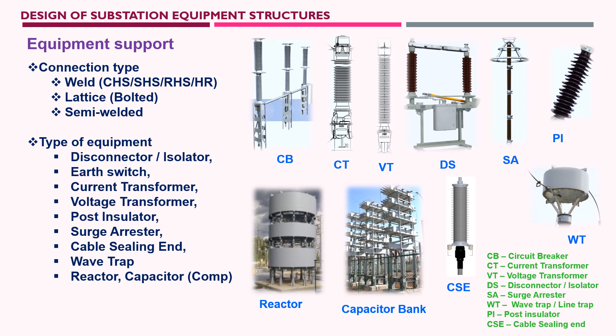Welded type is a square hollow section or circular hollow section welded at the top and bottom to become a rigid support for equipment. The second type is a lattice support structure, where all four legs — made of angle section, UPN, or channel section — are connected with diagonal or horizontal bracings using bolts. This lattice support structure is a flexible support structure.